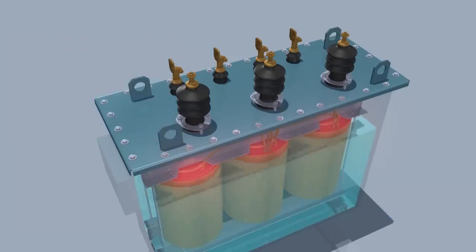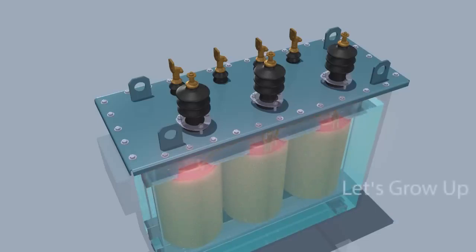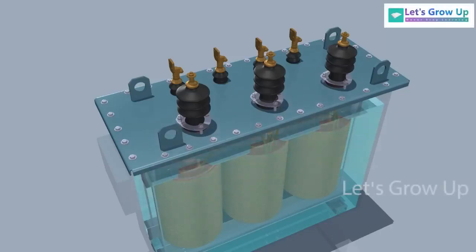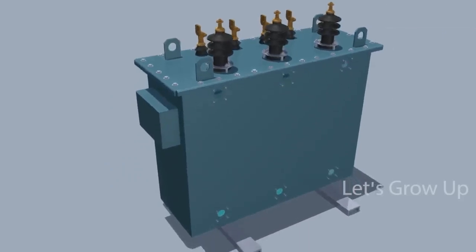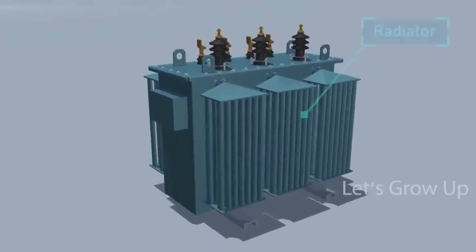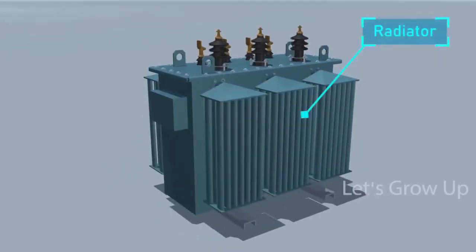The main role of transformer oil is to act as a coolant and to insulate. Transformer oil is an exceptional heat conductor, and can effectively reduce the copper coil's temperature, stopping them from burning. Not only that, external cooling tubes, or radiators, are there. The radiator of the transformer accelerates the cooling rate, thus it plays a key role to increase the loading capacity of an electrical transformer.